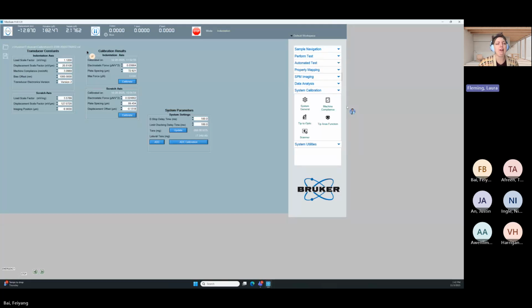I think so. Here you have your load scale factor and displacement scale factor and a few other settings that we will go over in the course of training. The transducer electronics version we don't really talk about, because it's version 2, and that's always going to be true. These might change slightly, but we'll talk about how to change them and when you need to. Similarly, for the scratch axes, we will talk about this in depth when we get to scratch-specific testing, because I want to focus on indentation right now. But it should be noted that we also use a transducer laterally, so we also need the same load scale factor and displacement scale factor for the lateral transducer.